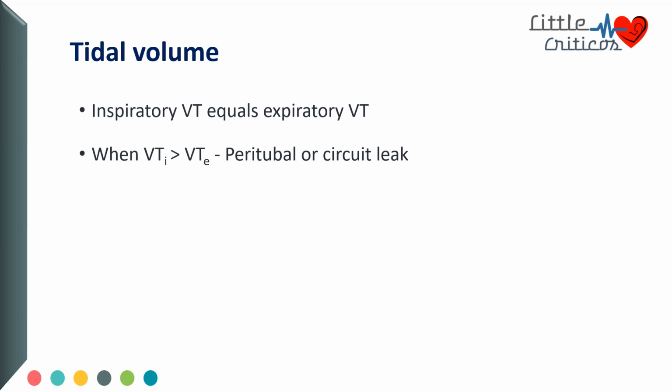The inspiratory tidal volume equals expiratory tidal volume. When the inspiratory tidal volume is more than expiratory tidal volume, it indicates a peritubal leak or a circuit leak. Always, we need to consider the circuit compressibility, which is the volume lost in the circuit. Most ventilators self-compensate for this loss.